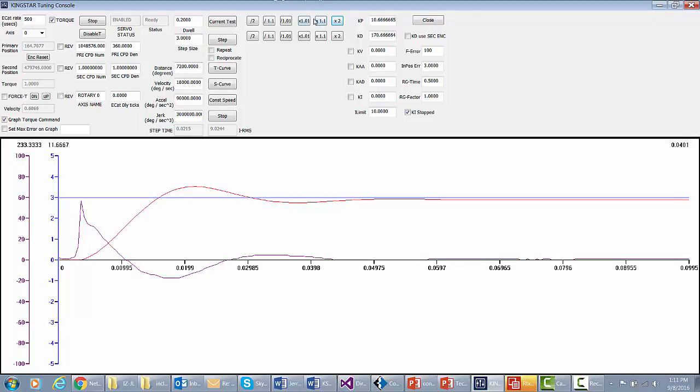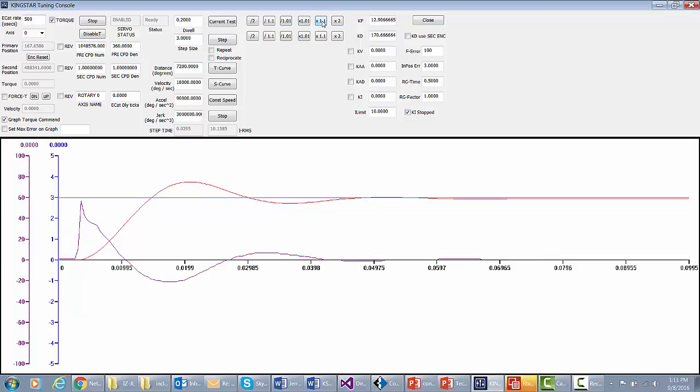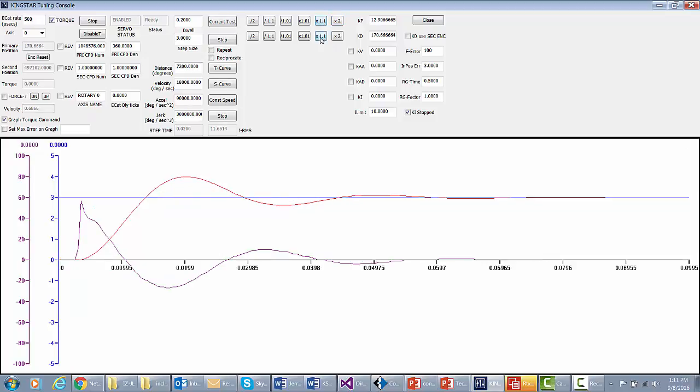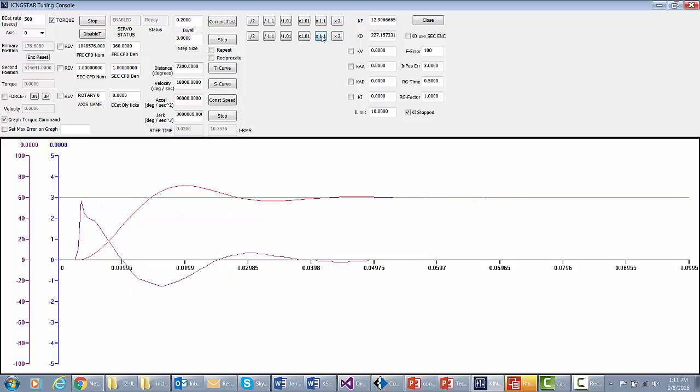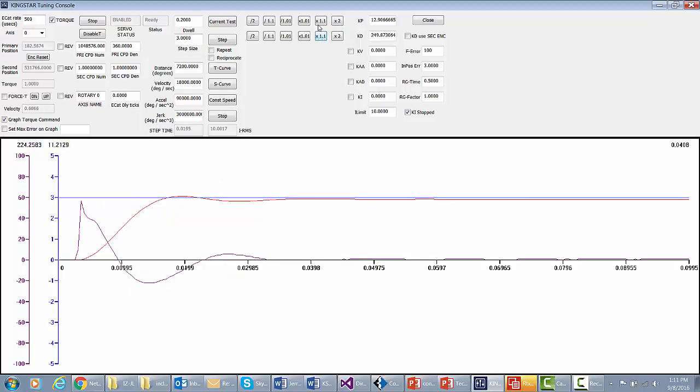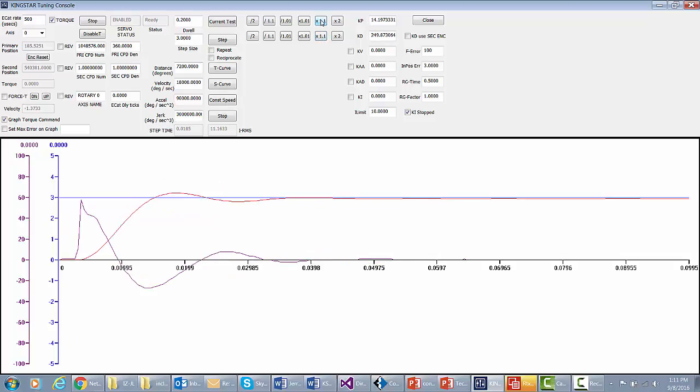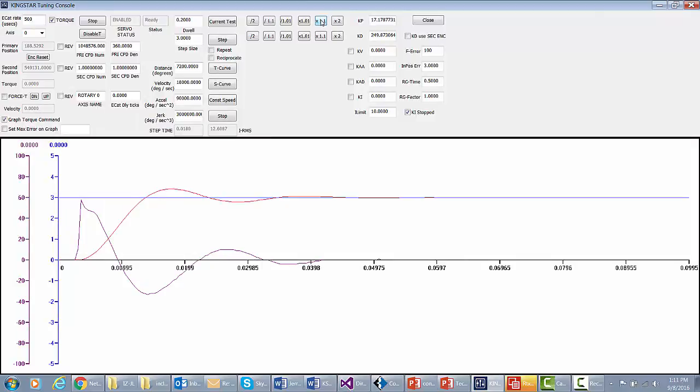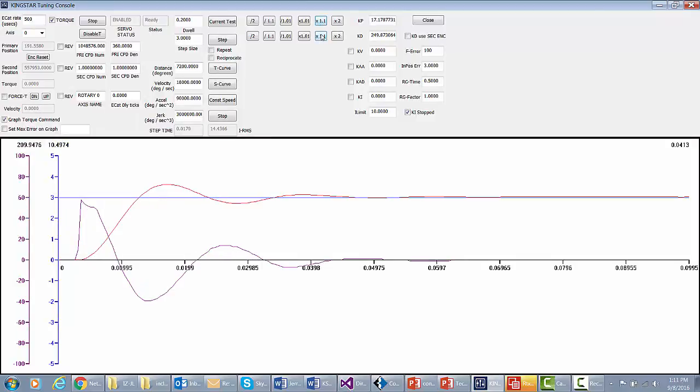Now I'm just going to go up by 1.1, so I'm just adding 10% here. Now I'll do Kd the same way, and I'll just click it a couple times, and we'll bring that back down, add some more Kp. Again, Kp is response. Kd is stability.